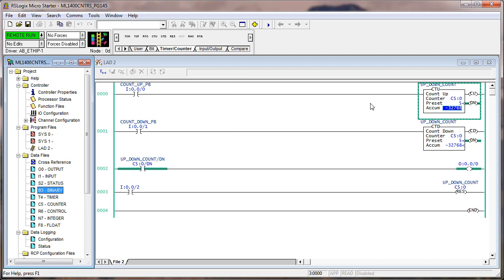That might be troublesome for your thinking, but it's something to be aware of. When working with the counter at -32,768, if I count up, it goes back towards zero. If I go down one more time, I go the other direction. Think of these numbers in a circle — you start at zero, increase and it forms half a circle. At the other side is 32,767. Go one more and you're at the lowest negative value, then back around the bottom half of the circle right back to zero.